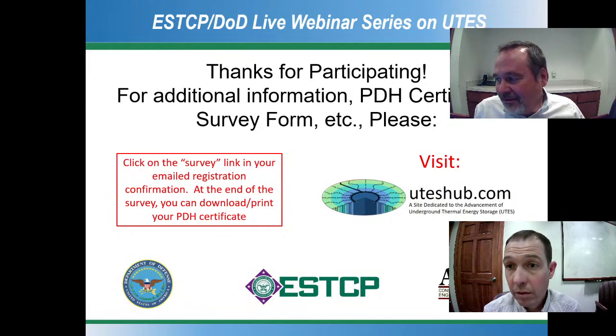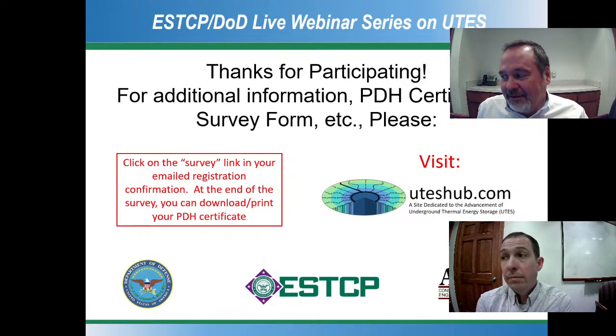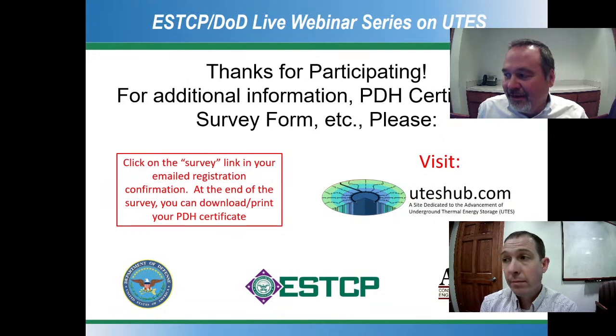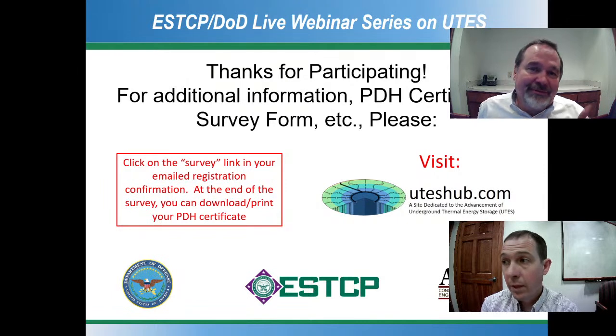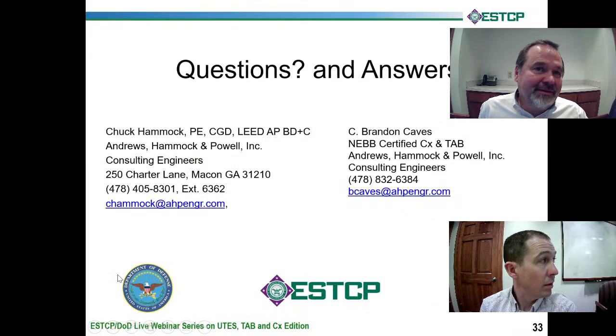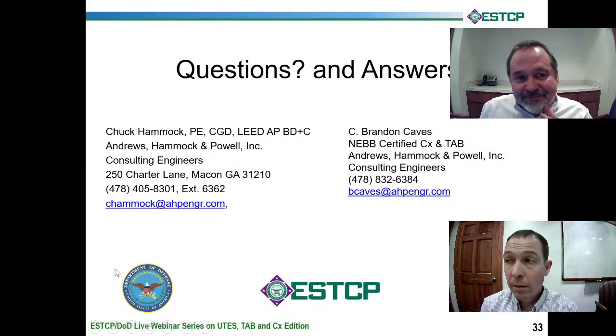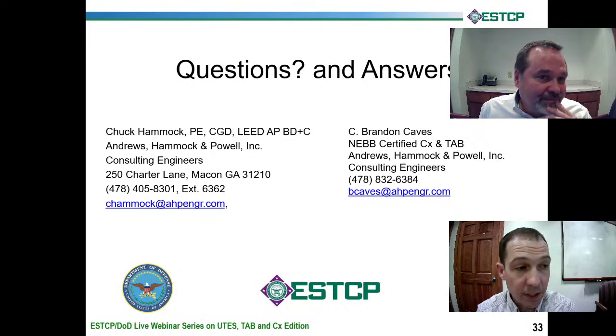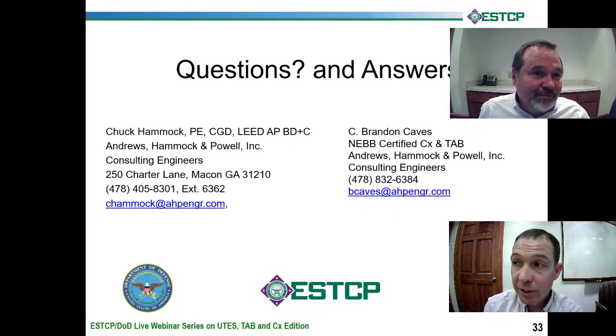The question is, how close to the 2 PSI do you recommend the pressure differential should get? So I think, Brandon, specifically, they're probably referring to the fact that the automatic flow control valves, we showed that they had an operating range of 2 to 32 pounds, but we probably need to go, I don't know if we can go back to that slide, that's probably too complicated, but the differential pressure transmitter is kind of covering, yeah. You want to do it, Joey, or me? Okay, all right. Yep. So that's a good question, and I don't think that you need to go down to 2 psi.